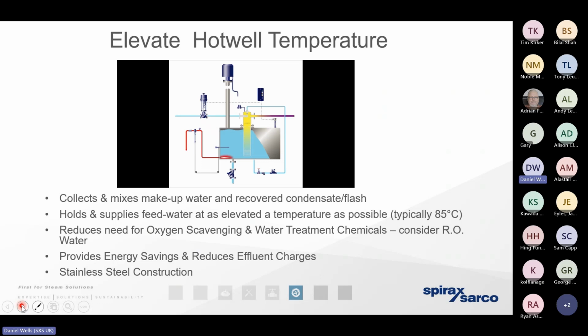High temperature hot water is self-explanatory. It means that we don't need to consume anywhere near as much gas in order to bring that water up to the point where we're producing steam again. Now, there's a very quick rule of thumb for you here: if we're able to elevate the temperature of the water in storage by 6 degrees, up to a maximum of 85 degrees, we expect to see a cost saving on our fuel of 1% straight away. It's a very, very quick win. How do we keep the hot well at a nice high temperature? We recover as much of that hot condensate as we possibly can.